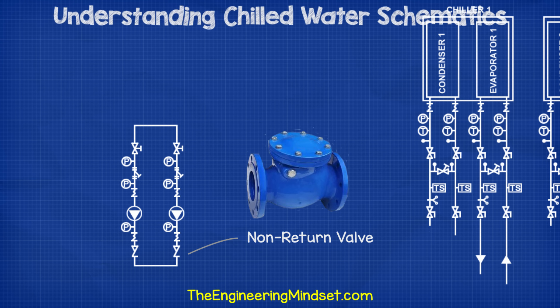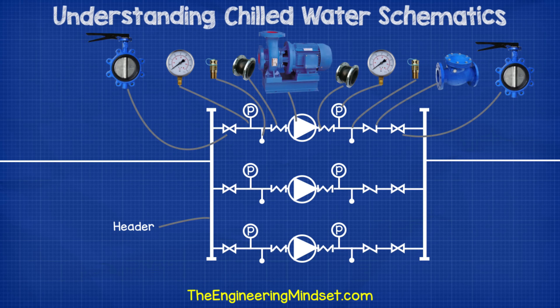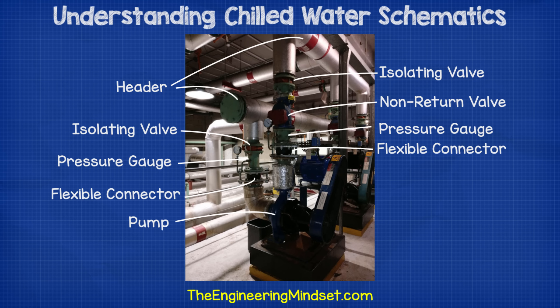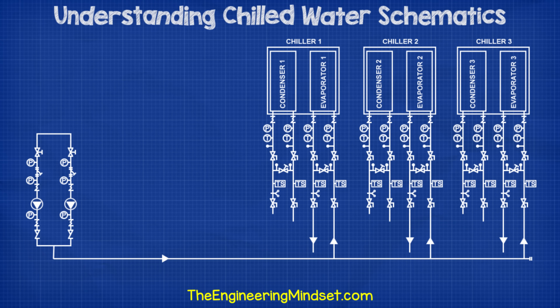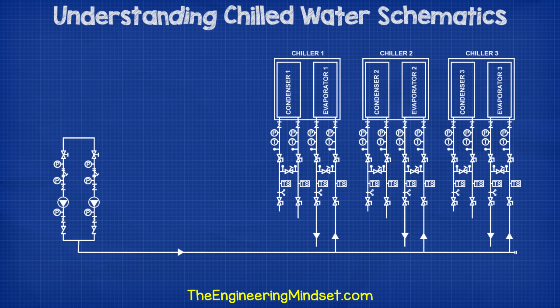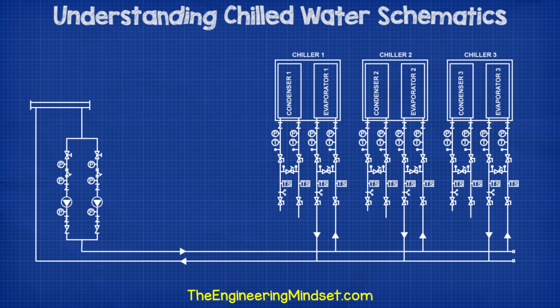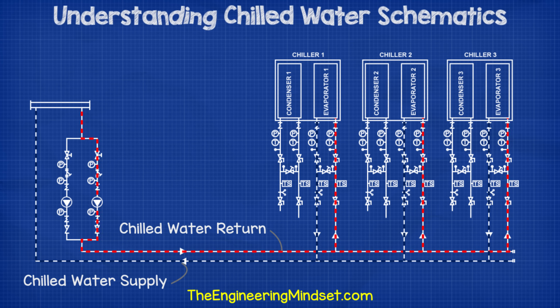Notice that this design doesn't have a second isolating valve past the non-return valve, but in newer systems you will usually find there is one. In the real world, it will look something like this, and this is for a centrifugal pump set. We know the pumps need to push water through the chiller, so we can connect the pump sets to the chiller's evaporator inlets. Chilled water is generated in the evaporator, so we'll need to connect that back around to the pumps to create a circuit which will distribute the chilled water.